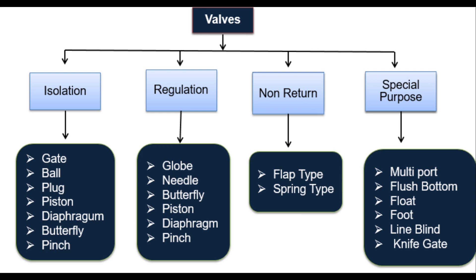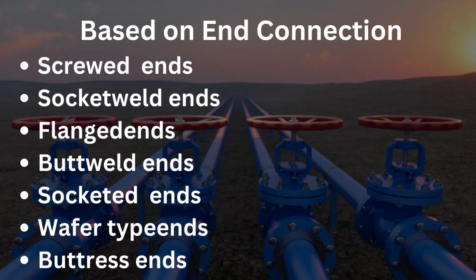Isolation type valves are used to turn on or off the flow, and include gate valve, ball valve, plug valve, piston valve, diaphragm valve, butterfly valve, etc. Valves used to regulate or control flow are classified as regulation type, including globe valve, needle valve, butterfly valve, piston valve, etc. Non-return valves prevent backflow or return flow, and are further classified into flap and spring types. There are also special purpose type valves.